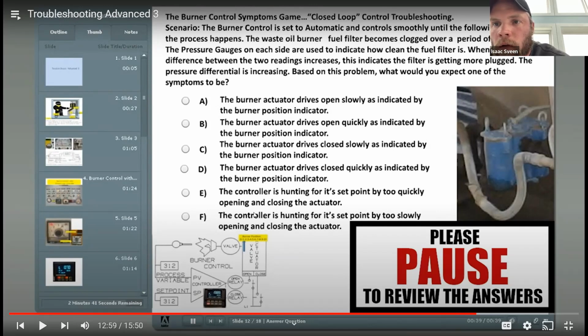Definitely going to be a couple in here. The controller's hunting for its set point. It's really not. So it's either open or close slowly, open or close quickly, or it's going to hunt excessively or slowly. Okay, I would go with it's going to open up slowly over time as the filter's getting clogged. Yep, nice.